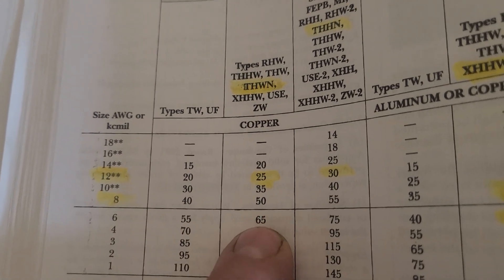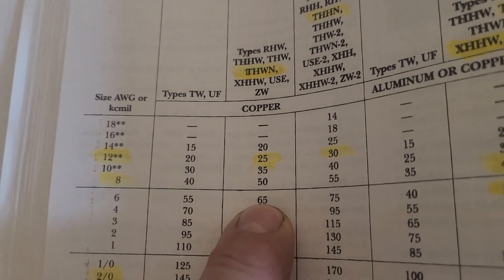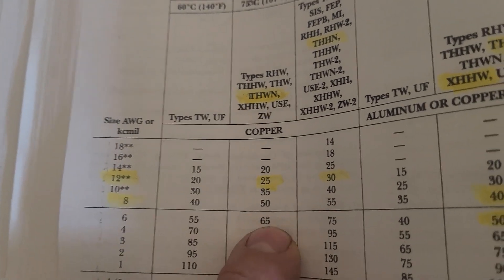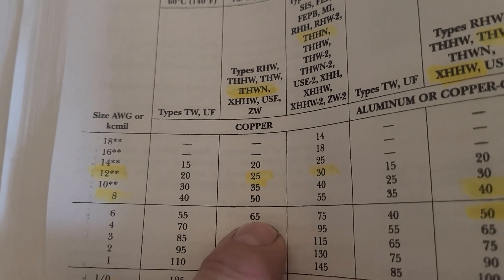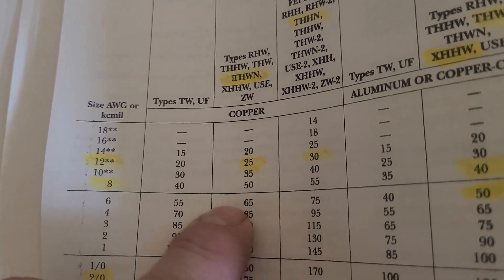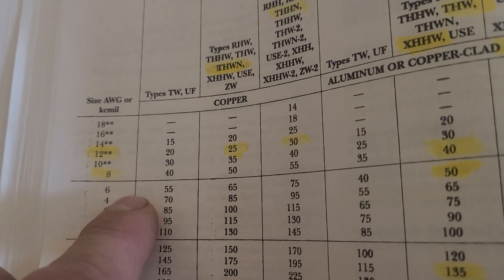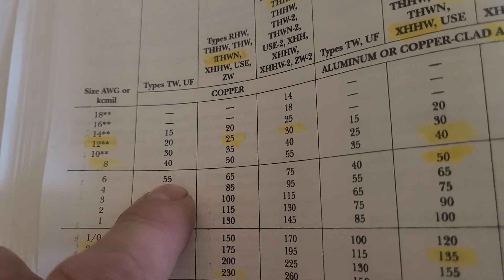Even if you were to get THWN, you're still good for 65 amps. See that right there? So anytime you want to rate your wire for, say, like a stove or an RV outlet, always rate it for number 6 copper wire.